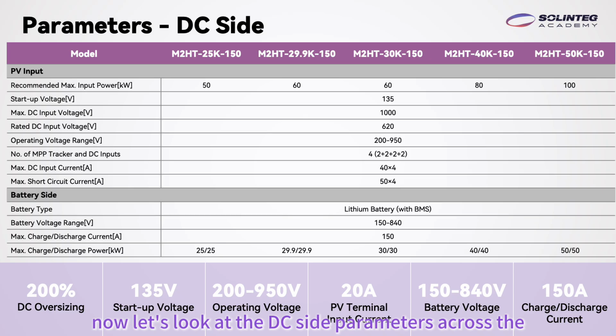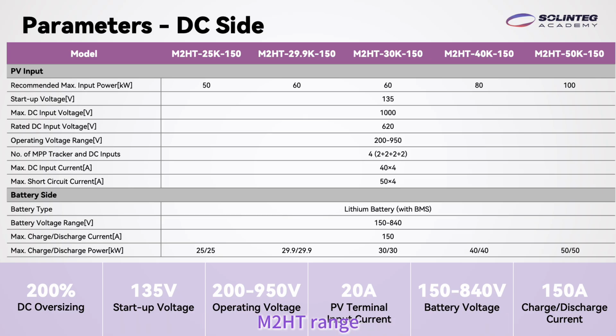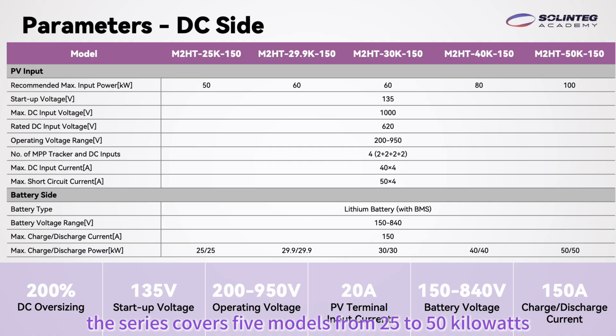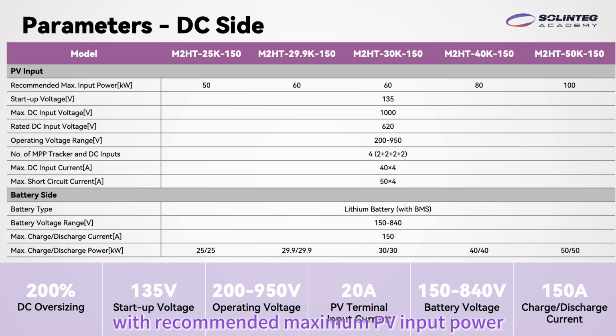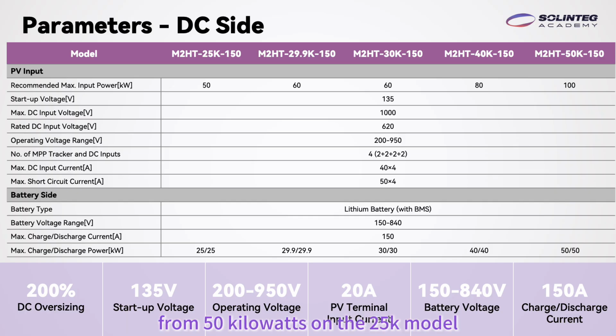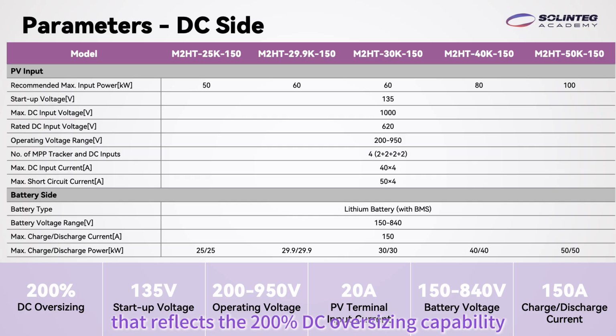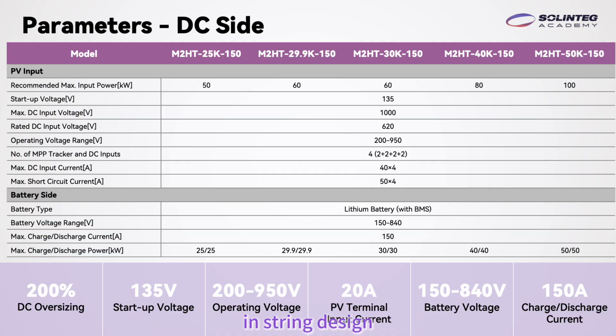Now, let's look at the DC side parameters across the M2HT range. The series covers 5 models from 25 to 50 kilowatts, with recommended maximum PV input power scaling accordingly, from 50 kilowatts on the 25K model up to 100 kilowatts on the 50K. That reflects the 200% DC oversizing capability, allowing installers to maximize solar harvest without oversizing the inverter itself. The inverter starts up at just 135 volts and operates across a wide voltage range of 200 to 950 volts, giving installers significant flexibility in string design.